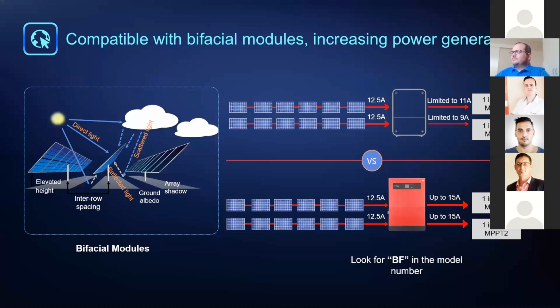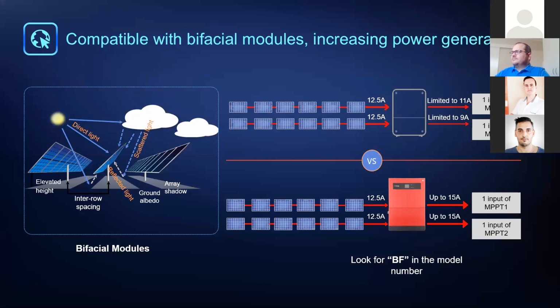Okay, another point worth mentioning, I'm sure we're all familiar with bifacial modules and the hype around bifacial, more specifically with ground-mounted and utility projects. But GoodWe has products available. If you look for these products, it's going to have BF in the model number of the product. They account for the additional current that you will see on the DC input side of the inverter, so up to 12.5 amps on the input. So we have products specifically made for bifacial modules, if you guys come across that.